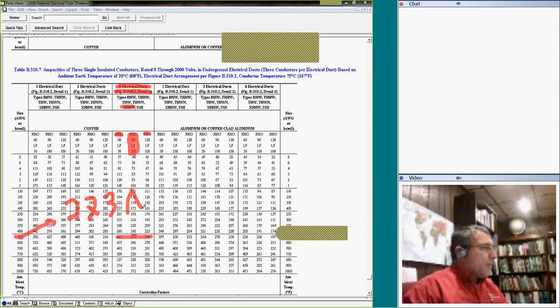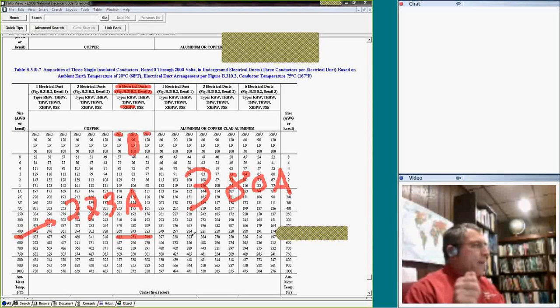You guys remember how much current a 500 kcmil can carry? A 500 kcmil can carry normally 380 amps. Can you see how low it can go under these circumstances, guys? From 380 amps all the way down to 273 amps. If I parallel 6 circuits in an underground concrete-encased duct, you no longer can use the 380. You have to go all the way down to 273 amps. 273 amps.